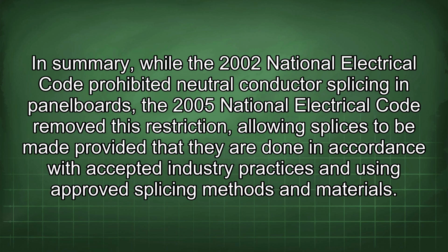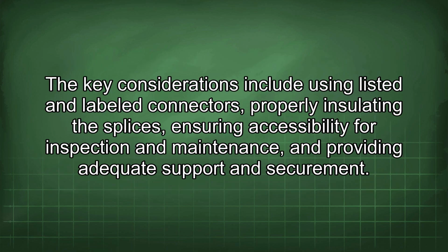In summary, while the 2002 National Electrical Code prohibited neutral conductor splicing in panelboards, the 2005 National Electrical Code removed this restriction, allowing splices to be made provided that they are done in accordance with accepted industry practices and using approved splicing methods and materials. The key considerations include using listed and labeled connectors, properly insulating the splices, ensuring accessibility for inspection and maintenance, and providing adequate support and securement.